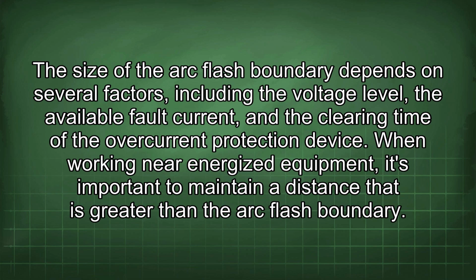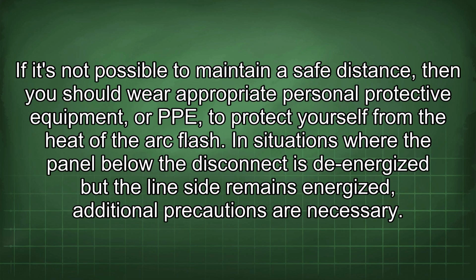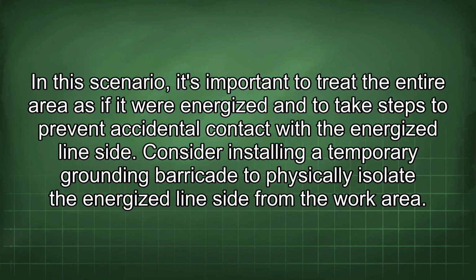When working near energized equipment, it's important to maintain a distance that is greater than the arc flash boundary. If it's not possible to maintain a safe distance, then you should wear appropriate personal protective equipment, or PPE, to protect yourself from the heat of the arc flash. In situations where the panel below the disconnect is de-energized but the line side remains energized, additional precautions are necessary. In this scenario, it's important to treat the entire area as if it were energized and to take steps to prevent accidental contact with the energized line side.